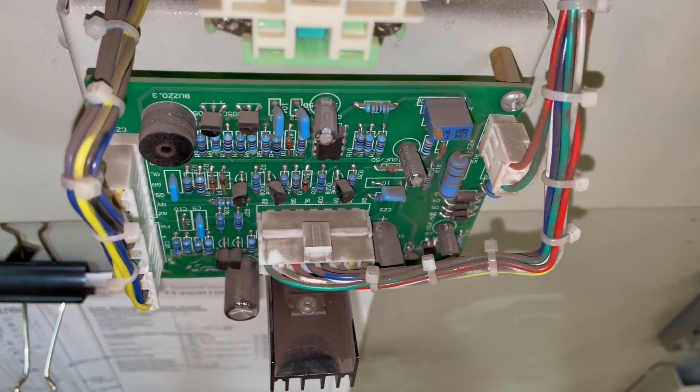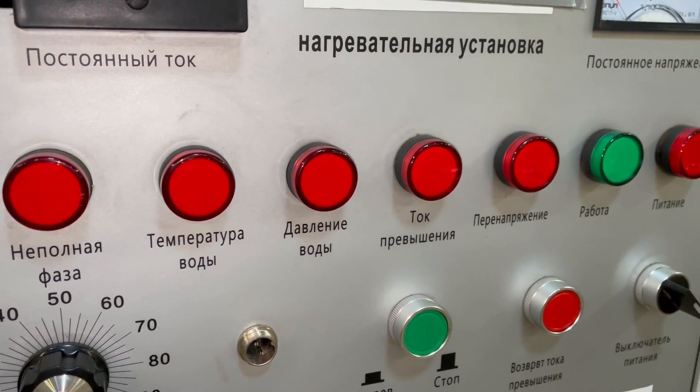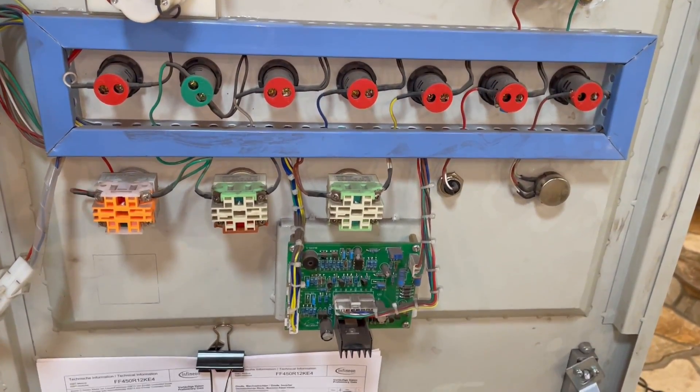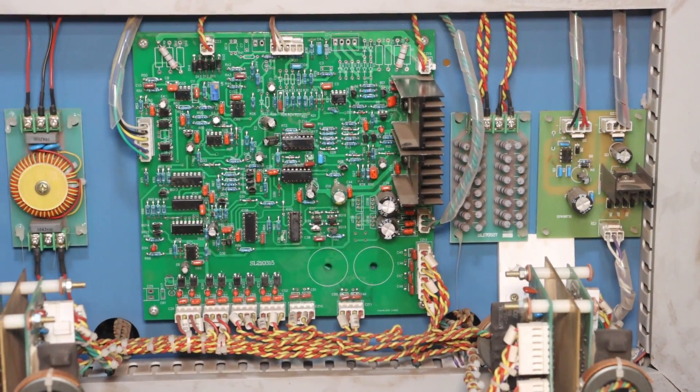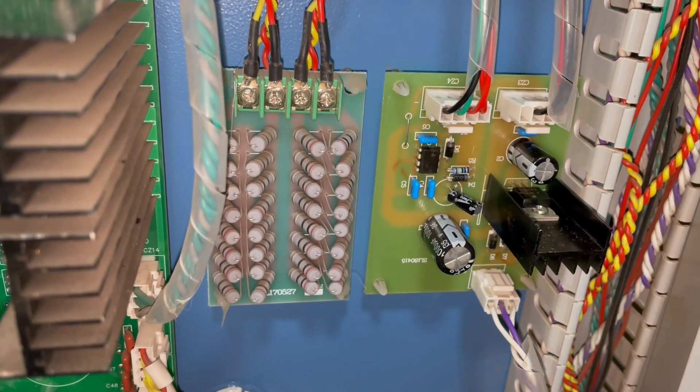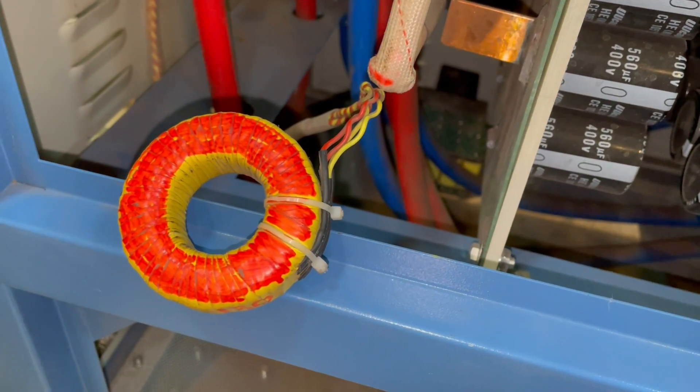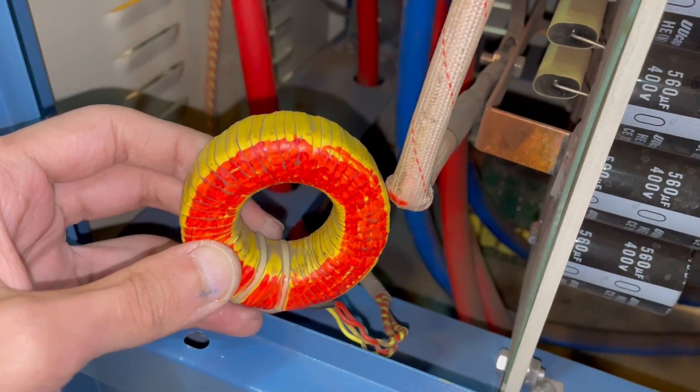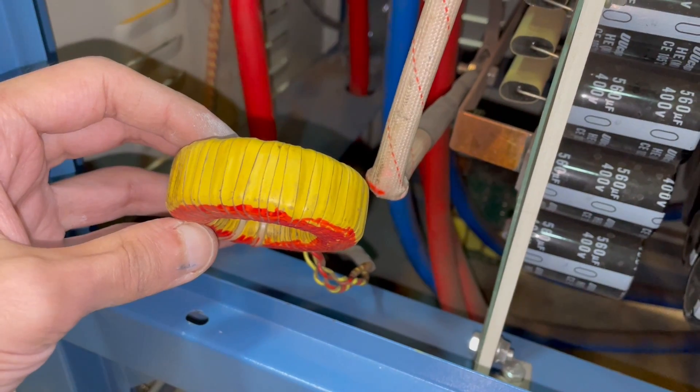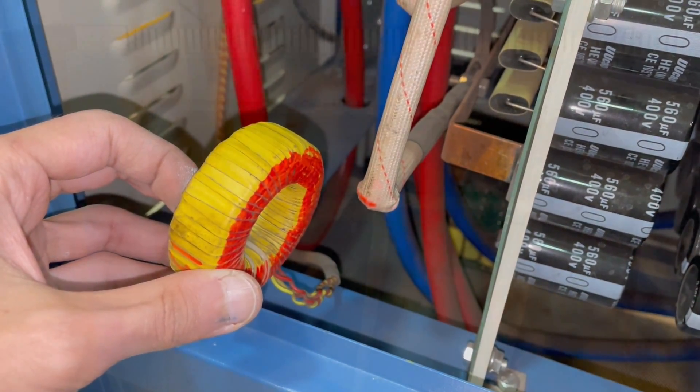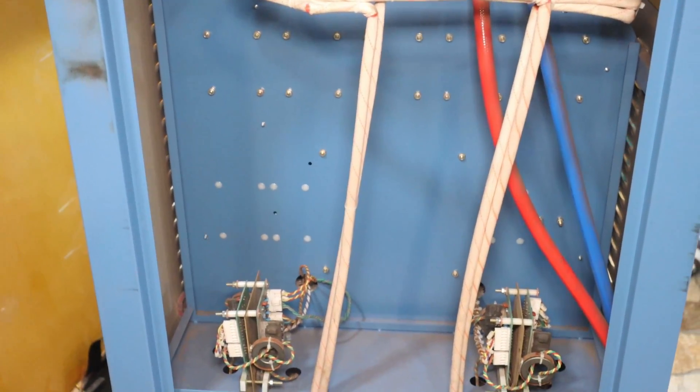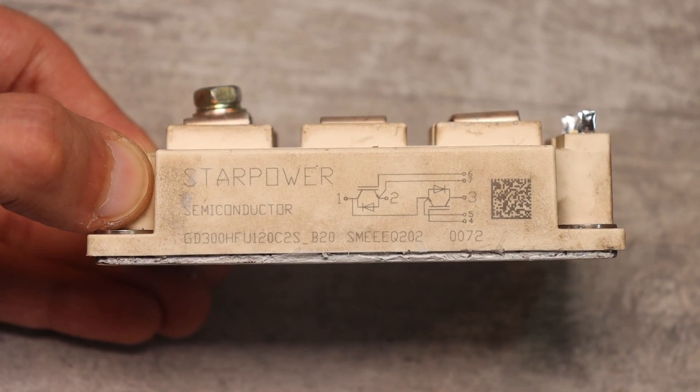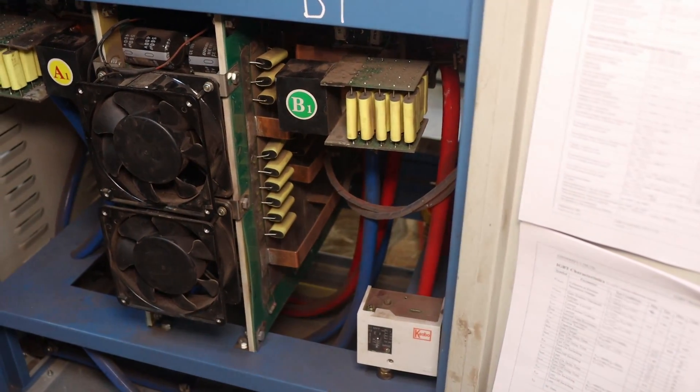This board also controls the alarm indicator LEDs. In addition, in case of problems, this board stops the operation of the control board and the unit turns off. Another board with a bunch of 2W resistors is for the current transformer, which as far as I understand performs a dual role. It monitors the output current of the inverter and is a part of phase-locked loop. There are eight drivers. Each of them controls its own transistor. There are four modules in total. They are half-bridge and so the number of transistors is eight.